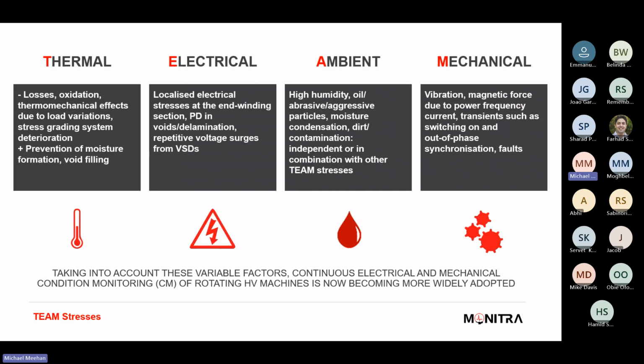So it's important to factor in the load cycle of a machine. How often does it start? And realistically, a machine that starts a lot, you're probably going to want to have some extra awareness on better ways to reduce those starts, or at least look at ways to control the starts, soft starts, things like that. It's just to sort of remove those mechanical stresses from the machine.